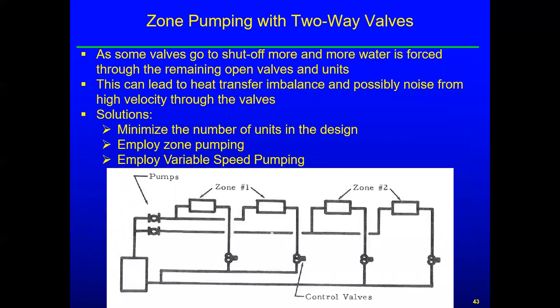Okay, so as some valves go to the shutoff position more and more, because that's going to up the pressure drop, or the pressure in the supply line, it's going to back you up the pump curve a little bit. And so the valves that are open, it's going to force more water through those valves, and then they're going to react. So this can lead to heat transfer imbalance, could lead to noise from high velocity through the valves. So there are some solutions to this.